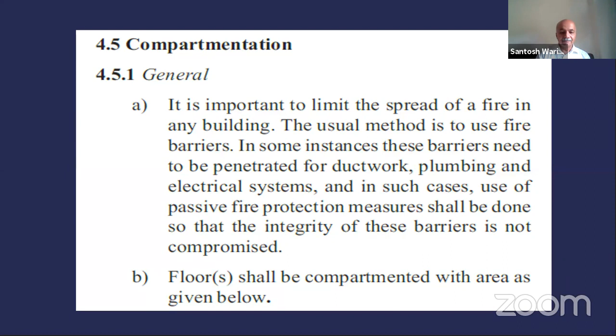The area of compartmentation is given as this. All the floors shall be compartmentalized or zoned with the area of each compartment being not more than 750 square meters. For all occupancies, it is a general statement. But if you are providing sprinklers, then there are some allowances given, as already told by Mr. V. Suresh sir. For a basement used only for car parking, it is 3,000. For a basement used for other purposes, such as services or electrical installations, it is 2,000.